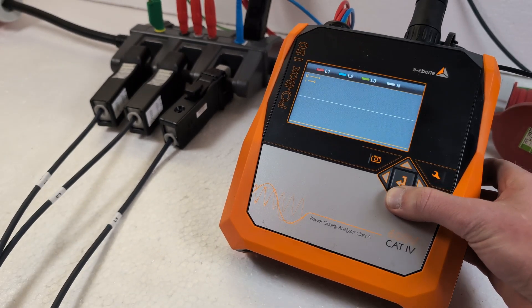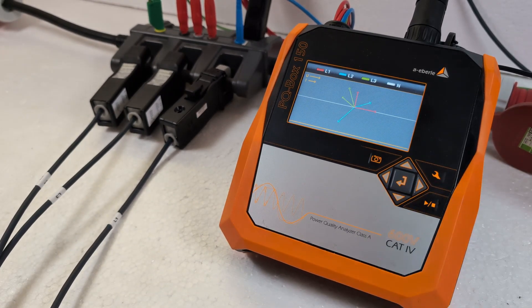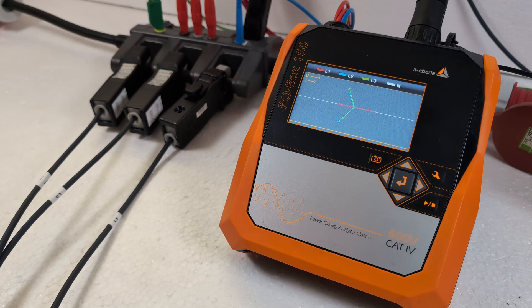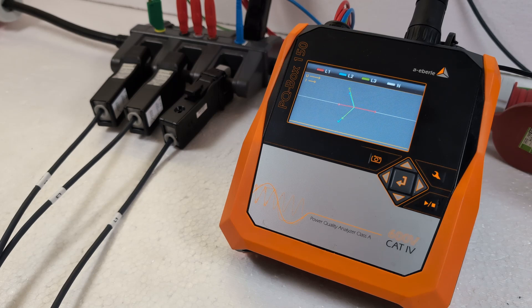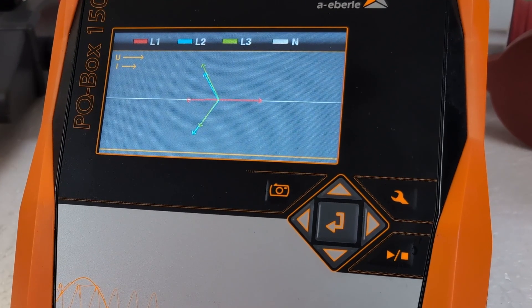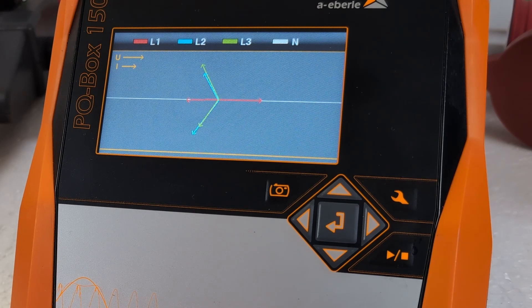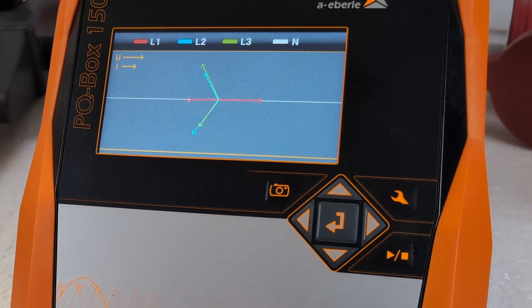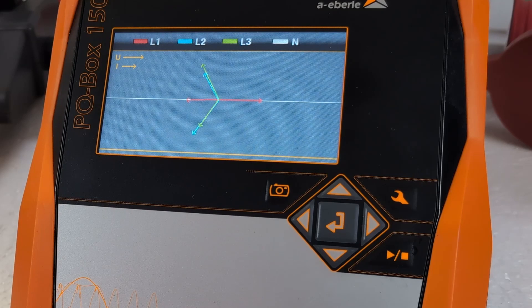I press the down arrow button and the PQBox shows me the phasor diagram. The colored arrows should actually point in the same direction. I can see that the current arrows do not match the voltage arrows.